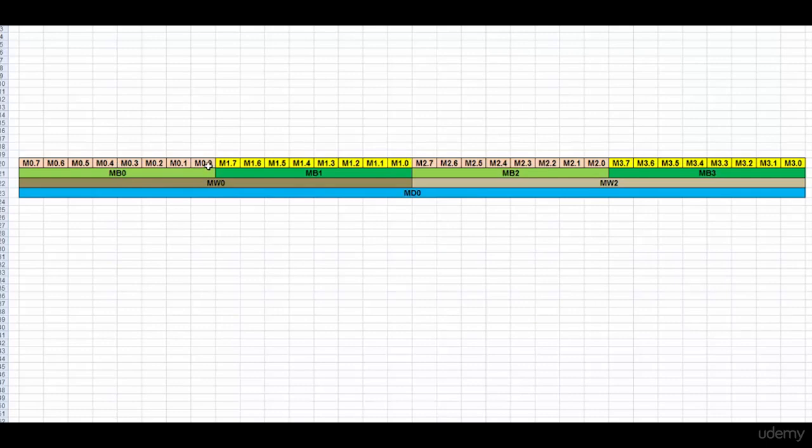And when we change to our organization block, how it looks in our PLC, we can see that the youngest bit is here, M0.0. Everything comes from the left to the right, so MB0, MB1, MB2, and MB3. MB, as we can see, is 1 byte. 1 byte has 8 bits. Next we have word, so a word has 2 bytes, MB0 and MB1, which of course have 8 bits each, so one word has 16 bits, and a double word has 32 bits, 4 bytes, and 2 words.